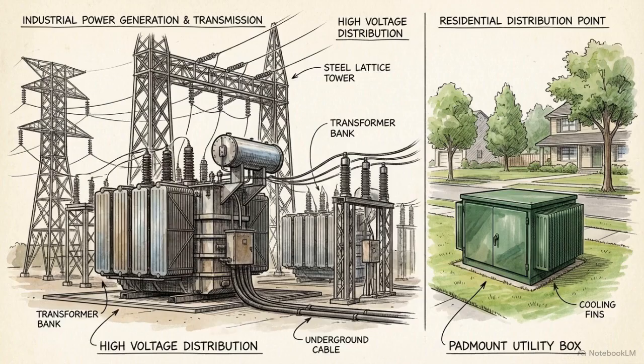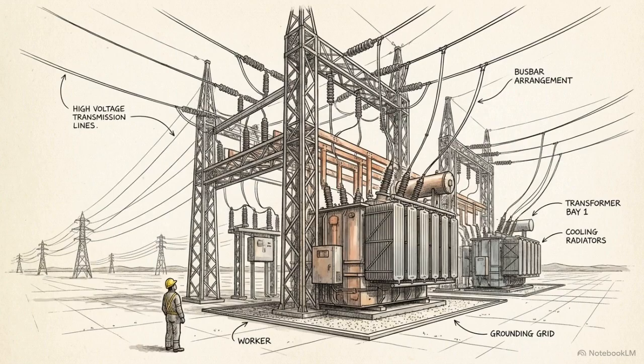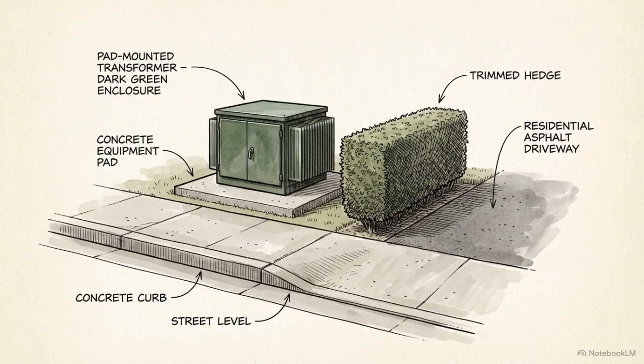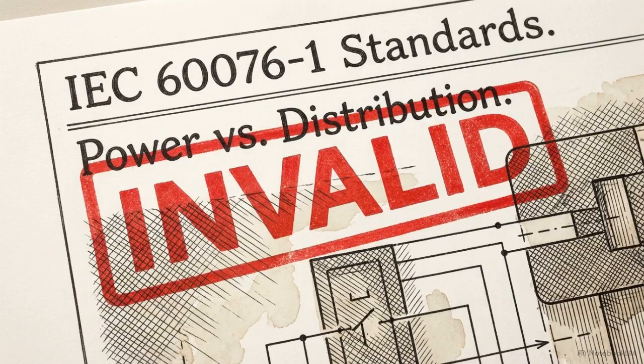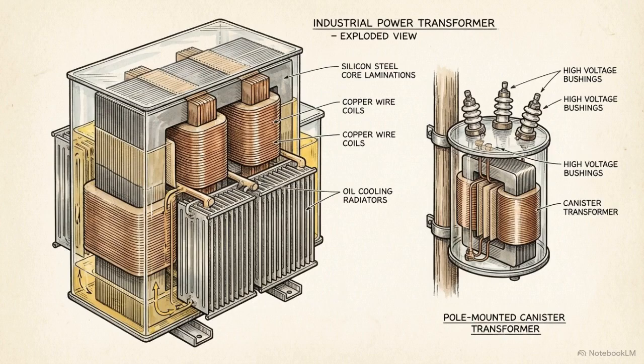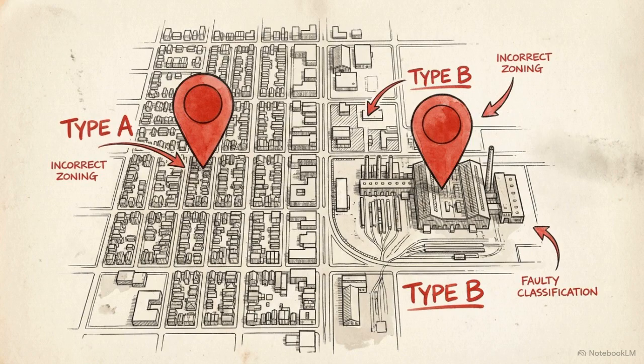A common colloquialism divides the market into two distinct categories: power transformers and distribution transformers. The industry shorthand assumes a power transformer is a massive multi-ton unit used exclusively for high-voltage transmission on the macrogrid. Conversely, it assumes a distribution transformer is a small, low-voltage unit dedicated to end-user delivery. But the strict truth is that IEC engineering standards do not recognize a physical or structural difference between these two terms. They are all technically power transformers. Every single unit is executing the exact same core or shell type induction using the exact same four materials. Mislabeling units based on where they sit on the grid creates false assumptions about their internal physics.